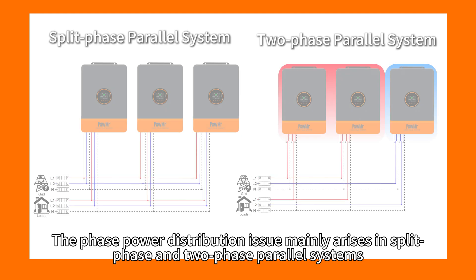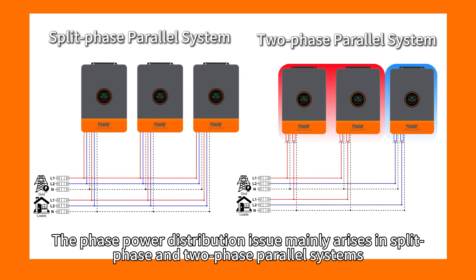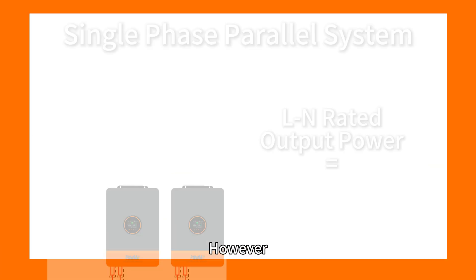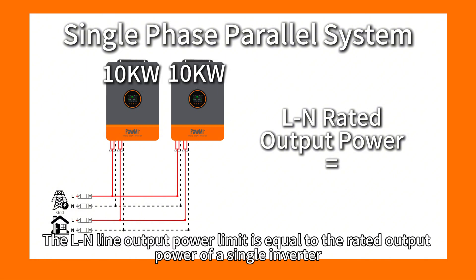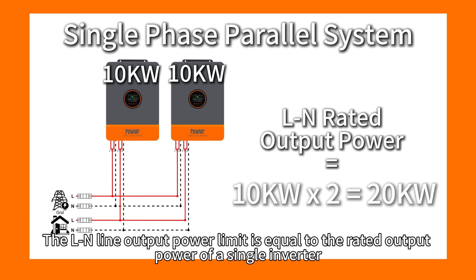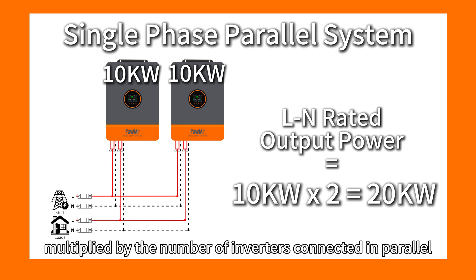The phase power distribution issue mainly arises in split-phase and two-phase power systems. However, we can understand the basic principle from the single-phase power system. The L-N line output power limit equals the rated output power of a single inverter multiplied by the number of inverters connected in parallel.